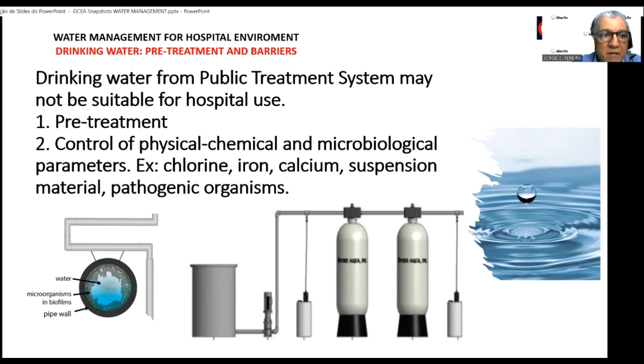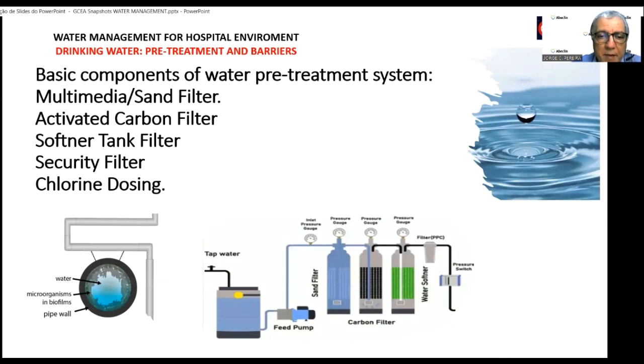Drinking water from the public treatment system, even with all its parameters within legal limits, can be a dangerous threat to our patients as well as to the hydraulic infrastructure and the secondary water system, such as reverse osmosis. Normally, the pre-treatment system consists of a multimedia filter to control suspended materials, an activated carbon filter for chlorine control, a softener filter to control water hardness, and a security filter to control microorganisms. And after all this system, you must have one chlorine dosing to reconstruct the chlorine doses.